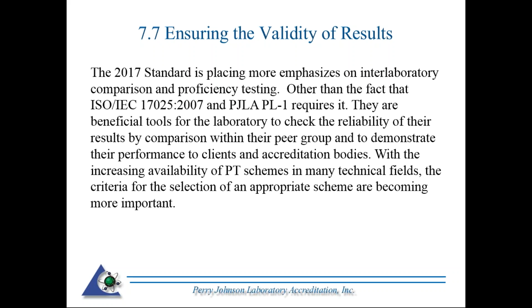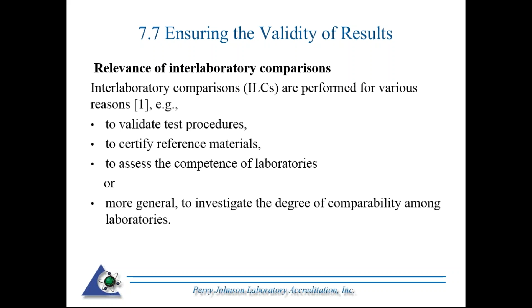So other than the fact that the standard requires it and PL1 requires it, interlaboratory comparisons are performed for various reasons. They can be utilized to validate test procedures, as in method validation. It's one of the methods that's listed. They can also be used to certify reference material, to assess the competence of laboratories, or, more generally, to investigate the degree of comparability among laboratories. Irrespective of the specific aims of the interlaboratory comparison, the results can be used by the participating laboratories to check the performance of their test procedure and/or staff, to demonstrate their competence toward clients and accreditation bodies, and also to gain useful information for the evaluation of their measurement uncertainty.